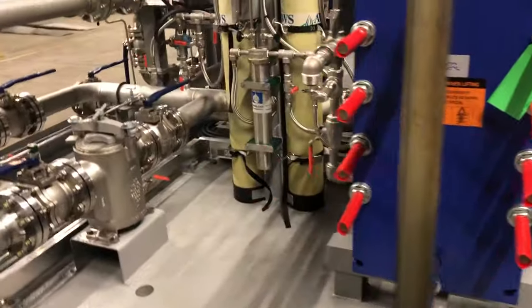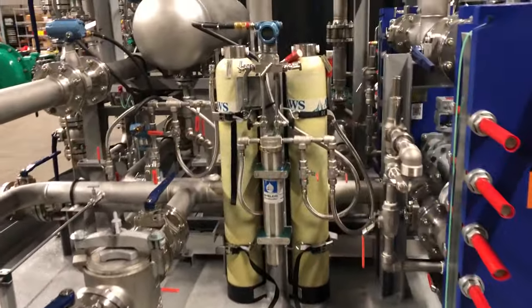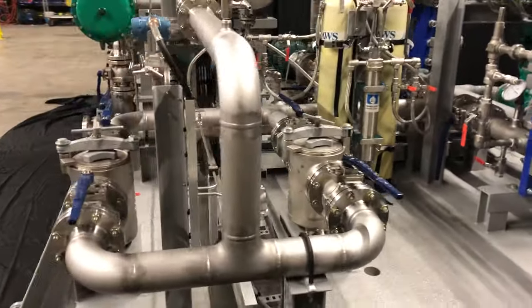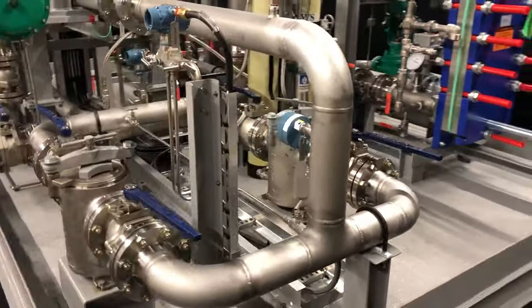On the back side here we have dual deionizing tanks for controlling the conductivity of the coolant in our system. We also have dual basket strainers for filtering out debris in the main coolant stream.